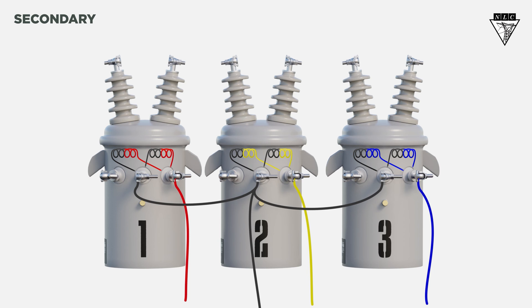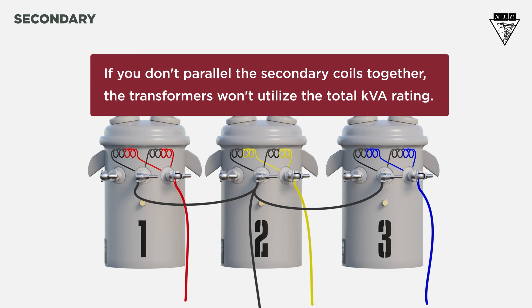Paralleling the secondary coils is necessary when only two secondary bushings are used. If you don't parallel the secondary coils together, the transformers won't utilize the total KVA rating.